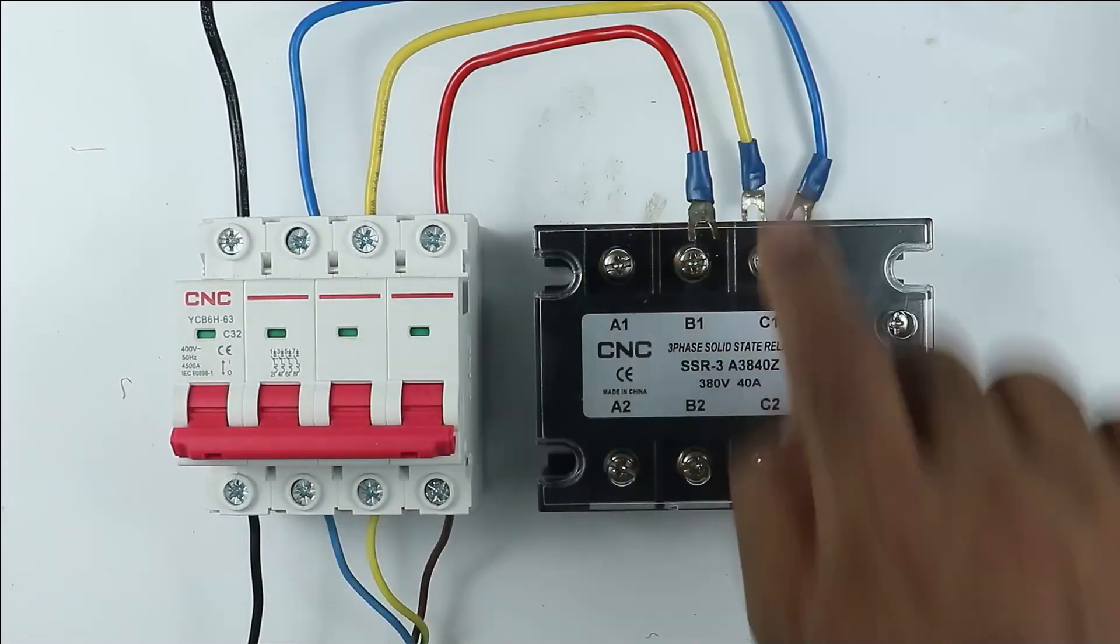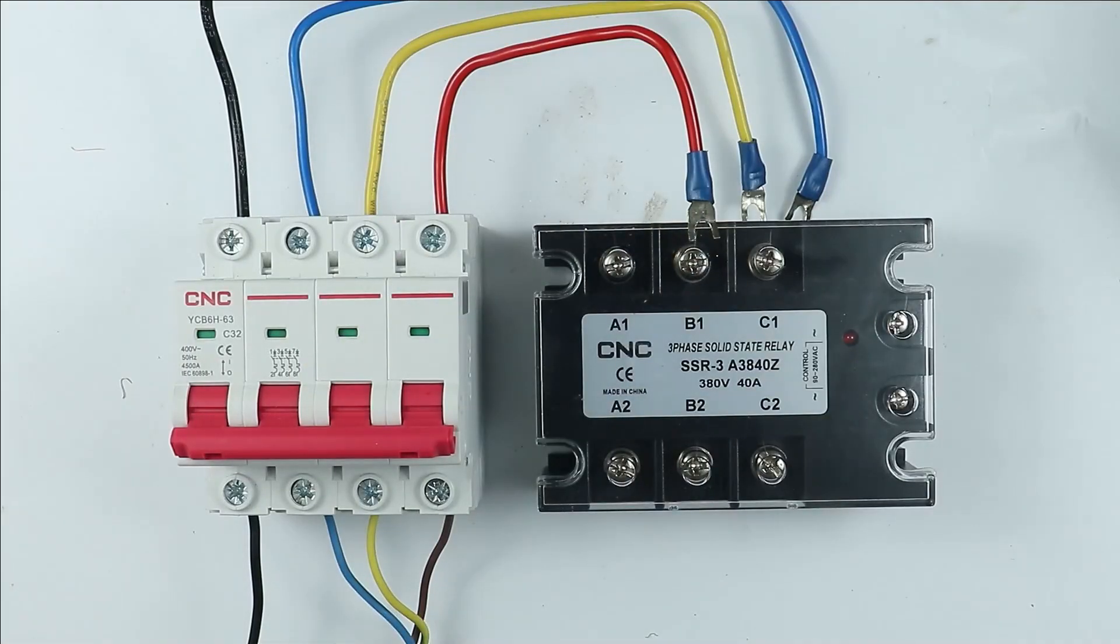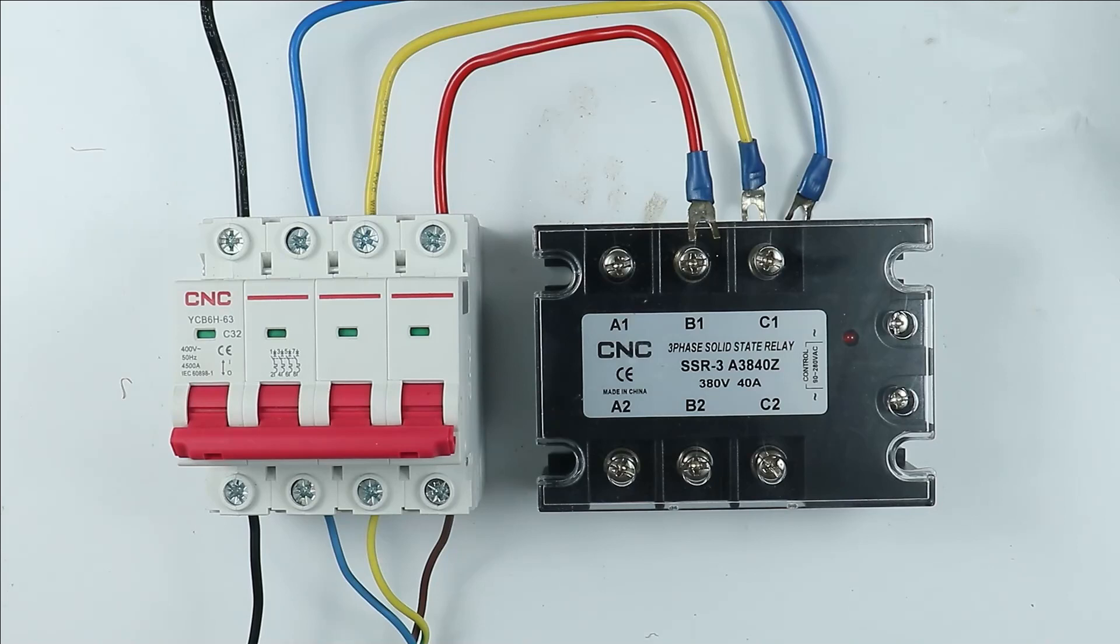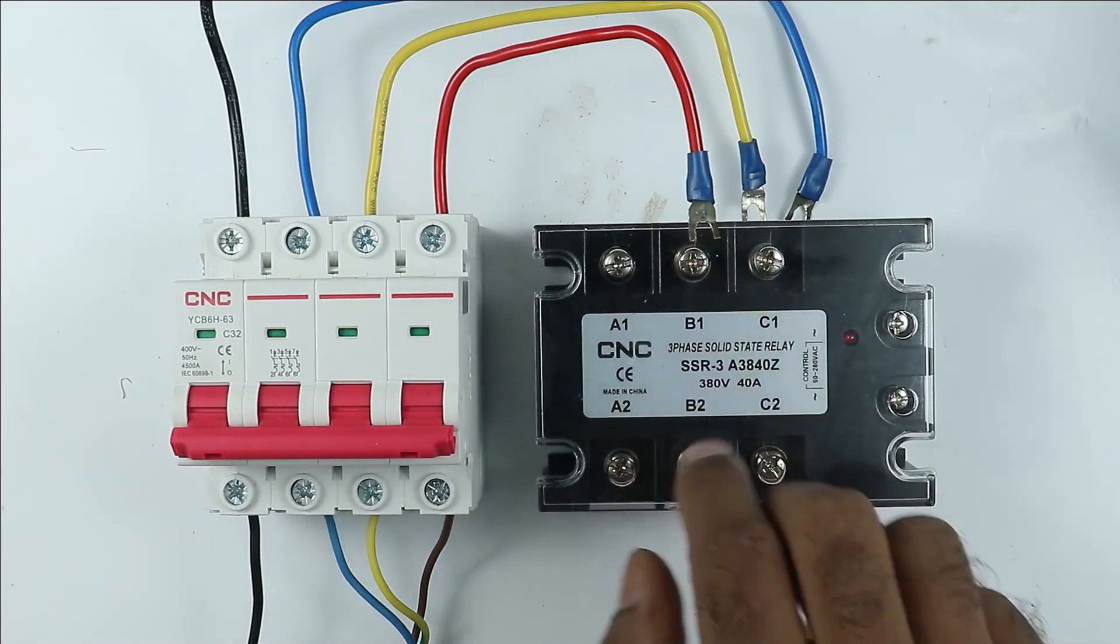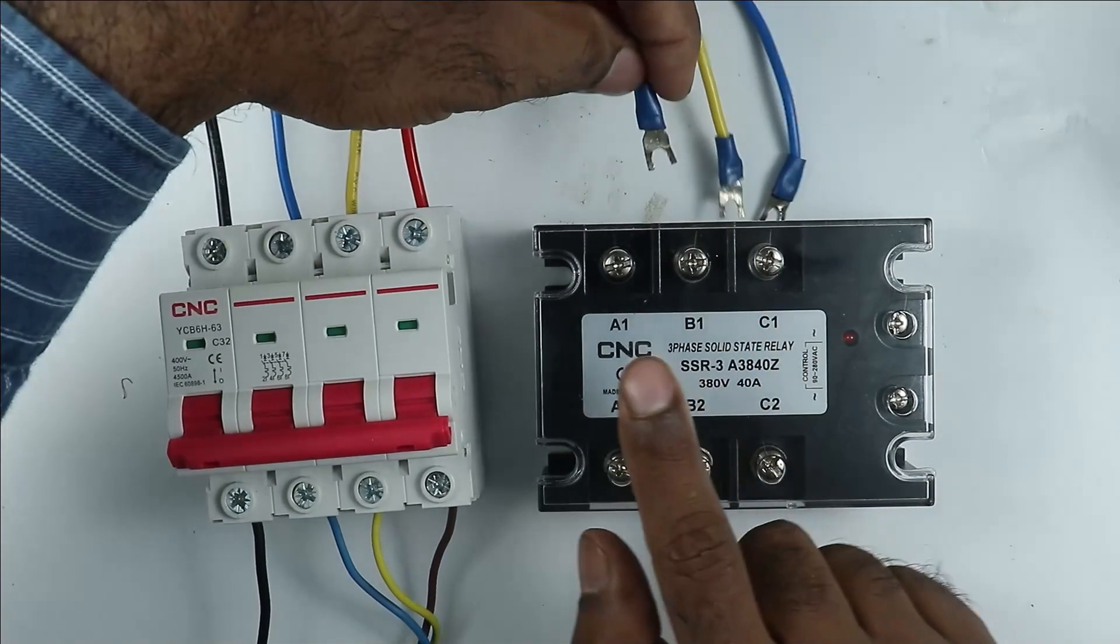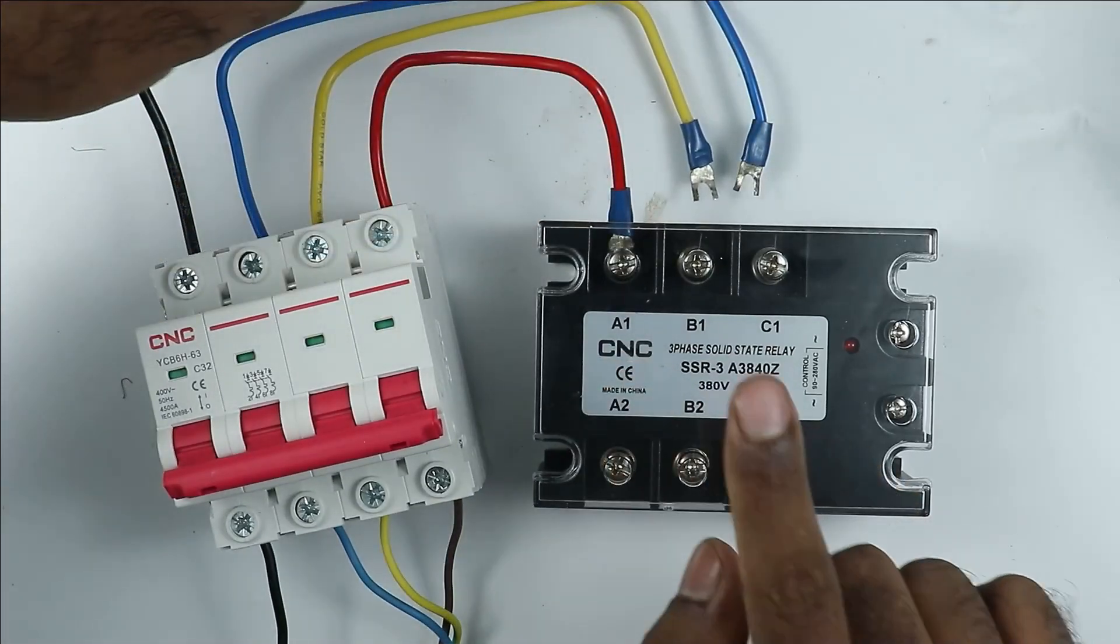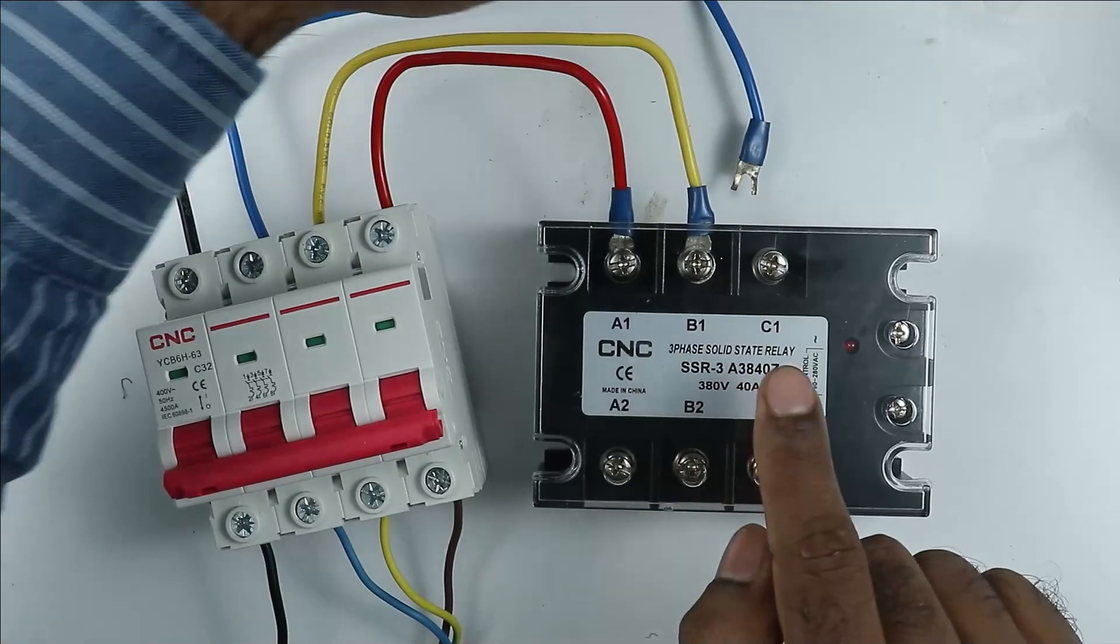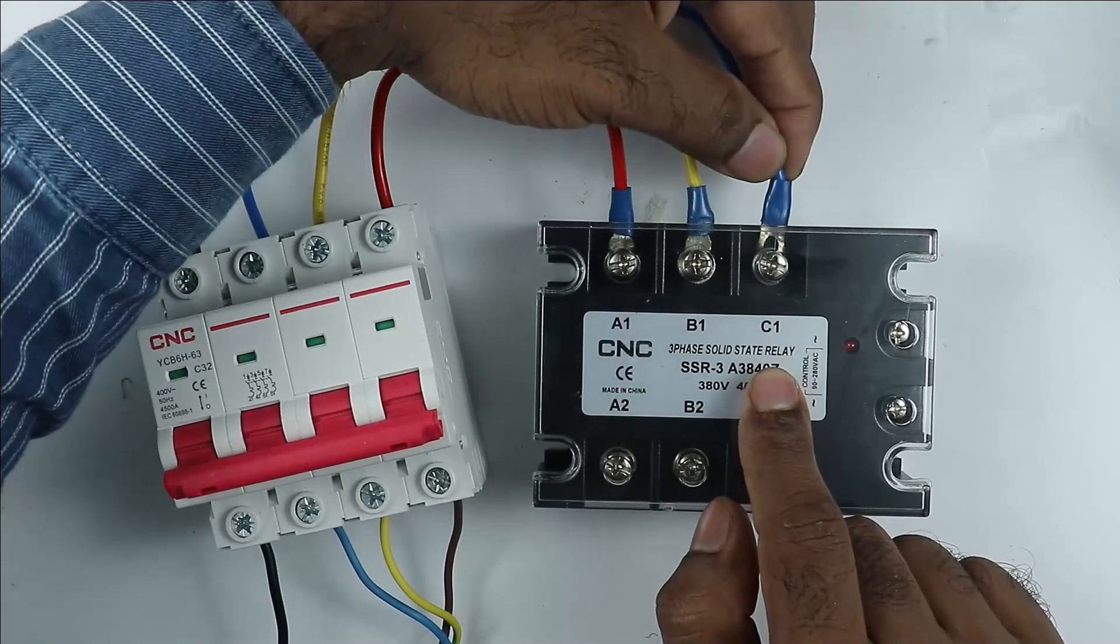First let us discuss about the power wiring of this relay. To perform power wiring what you have to do simply is the three phase incoming power supply you have, among the three, the R phase power supply, take the R phase supply and connect with A1 terminal. At B1 terminal connect Y phase power supply and at C1 terminal you have to connect B phase power supply.